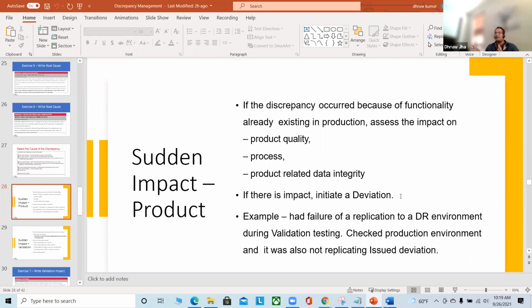Now each deviation is a process. A deviation is reportable to FDA, saying, hey, I have a deviation in my system, and that deviation can turn into a CAPA. So the moment it becomes a deviation and CAPA, it's directly connected to FDA. FDA needs to know about it. Then you're time bound. You have to fix it within that timeline. So all these things happen behind the back. Any question, any concern?